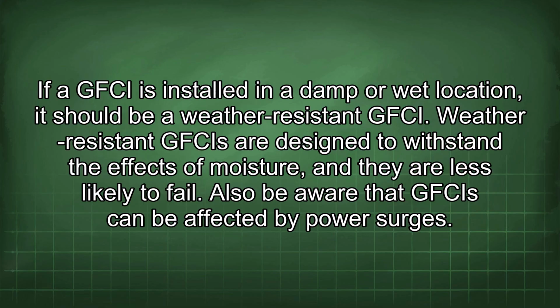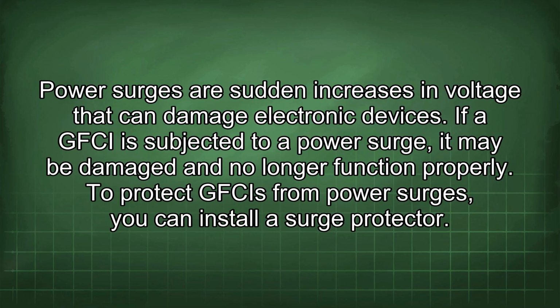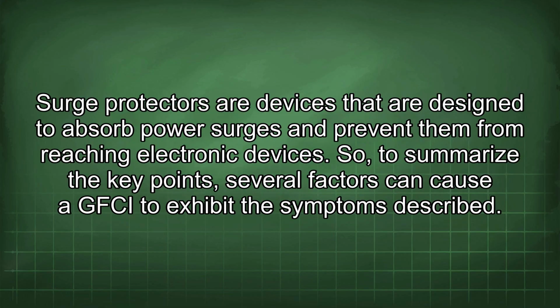Also be aware that GFCIs can be affected by power surges. Power surges are sudden increases in voltage that can damage electronic devices. If a GFCI is subjected to a power surge, it may be damaged and no longer function properly. To protect GFCIs from power surges, you can install a surge protector. Surge protectors are devices that are designed to absorb power surges and prevent them from reaching electronic devices.